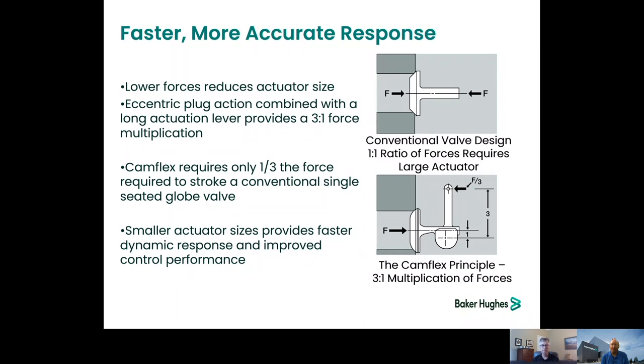And it's done using a spring and diaphragm, a rolling diaphragm actuator design. So you still get all the sensitivity that you expect from a spring and diaphragm actuator. In most control valves, spring and diaphragm actuators are still preferred because they provide the most sensitive, the finest control compared to pistons and other rotary designs, other actuator designs. So you get that, but in a very small package.